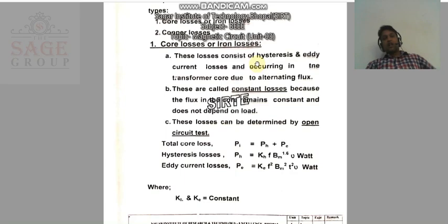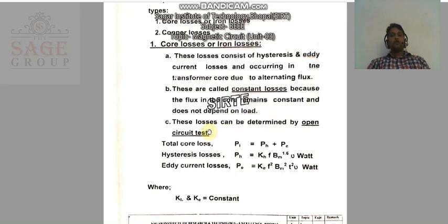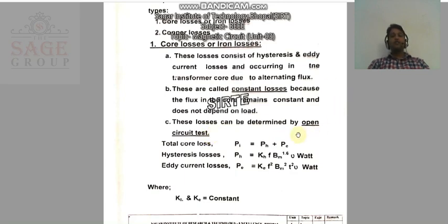These core losses consist of hysteresis and eddy current losses occurring in the transformer core due to alternating flux. They are also called constant losses because the flux in the core remains constant and does not depend on the load. These losses can be determined by the open circuit test, which we have already discussed.